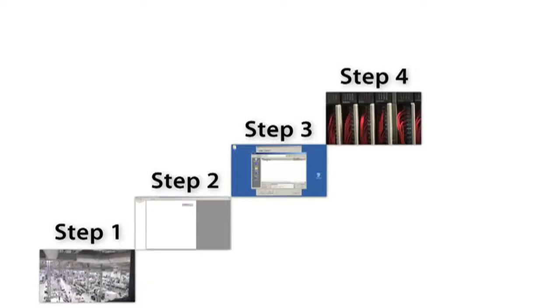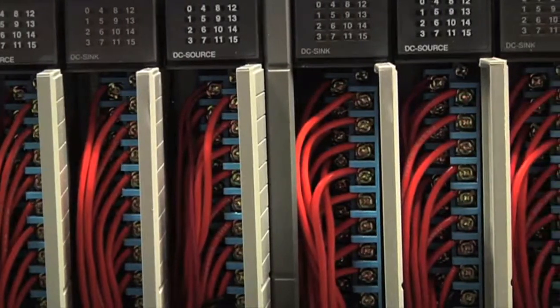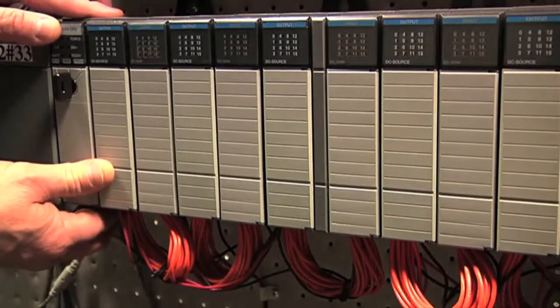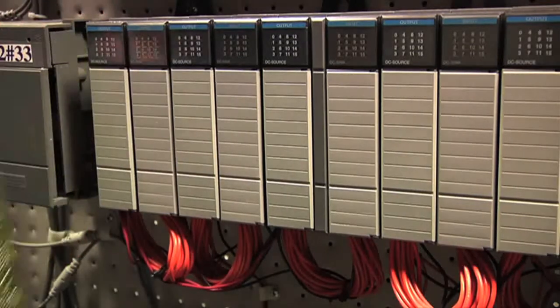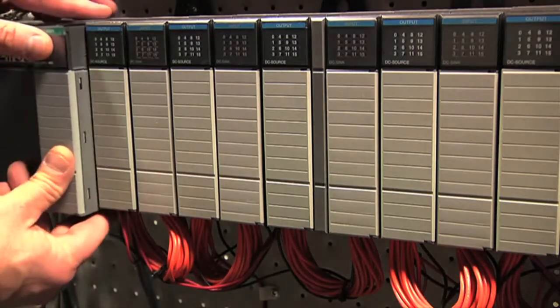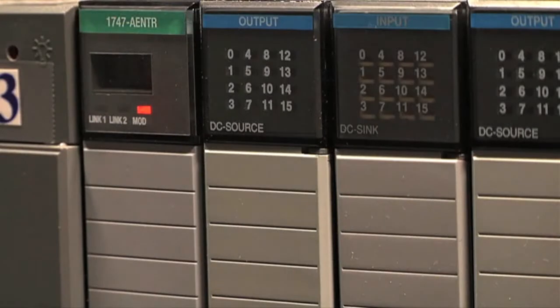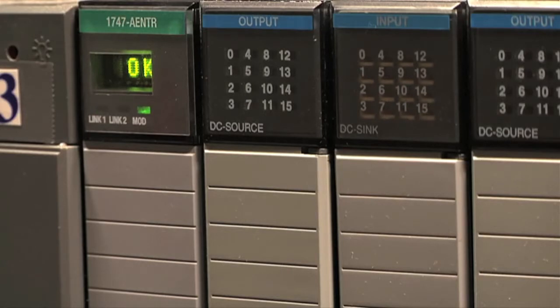Step 4. Mount and wire the CompactLogix system and replace the SLC first slot modules — that is the SLC processor or communication adapter module — with the SLC Ethernet adapter, the 1747AENTR. Utilizing this module allows you to retain your existing SLC-IO and preserve existing field wiring, while allowing your SLC-IO chassis to be controlled from your new compact Logix controller.